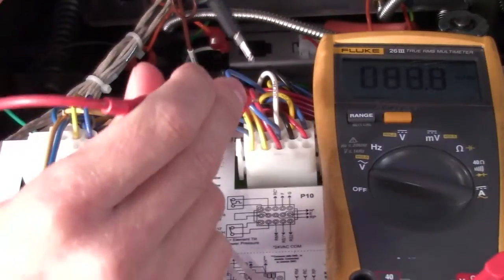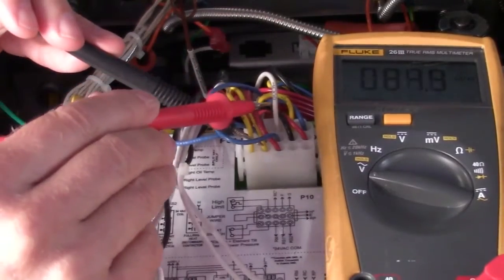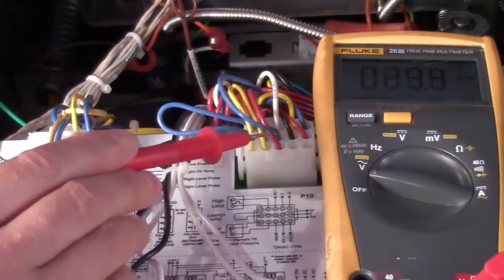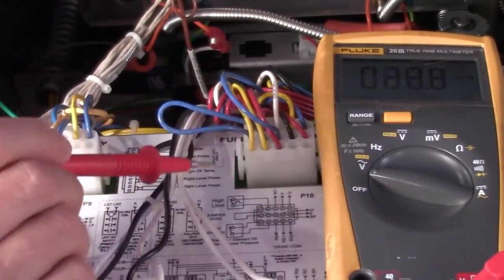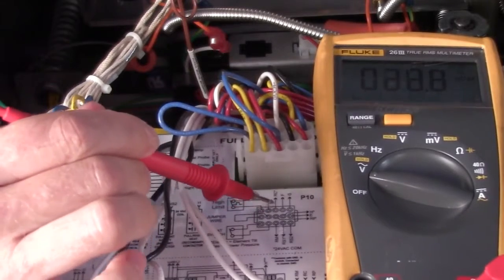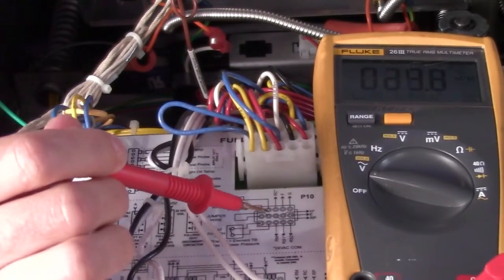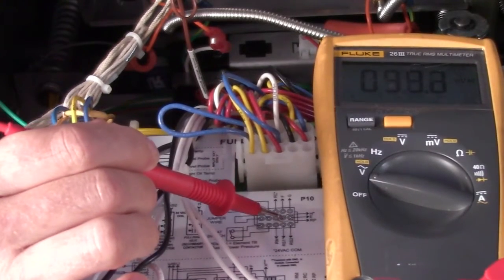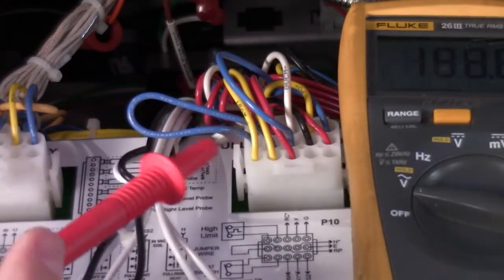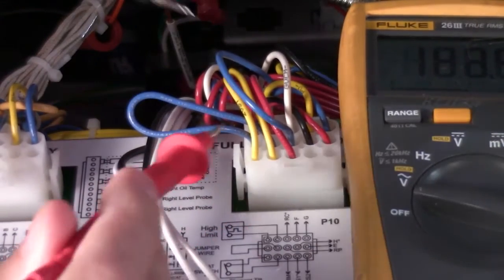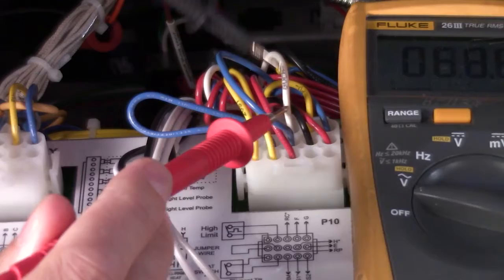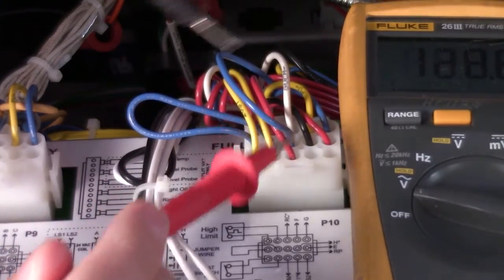First off, I can go ahead and check. We have the white wire right here, and then we have this blue wire. So it's going to be these middle two right here on the diagram. If you forget this and you're trying to remember which two, you've got to check it. It's going to be your white wire, blue wire. That's going to be out for your pilot.